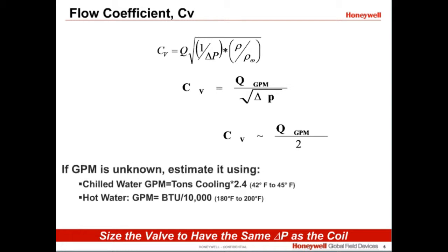If the flow rate is unknown, you can estimate it. For chilled water, multiply the coil's tons of cooling by 2.4. And for hot water applications, divide the BTU of the coil by 10,000 to get your flow rate in gallons per minute. Once you have calculated the CV, choose a valve with a CV as close to this number as possible.